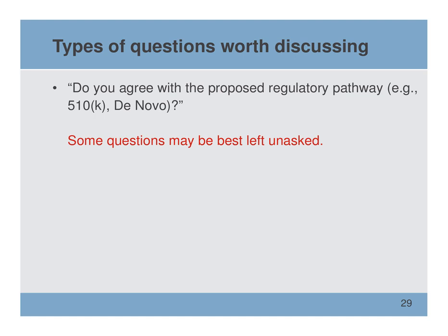So, don't ask if you should do a clinical study. Say, here's all our bench testing and animal testing. Are we done, FDA? Don't ask if they agree with your clinical study design, if you're a little bit worried about what they might say about it. In one sense, just sort of lay it out there. Ask them something like the acceptance criteria, the sample size. If they think you need a 2-arm study versus a 1-arm study, they don't like your control arm, they'll tell you about it.